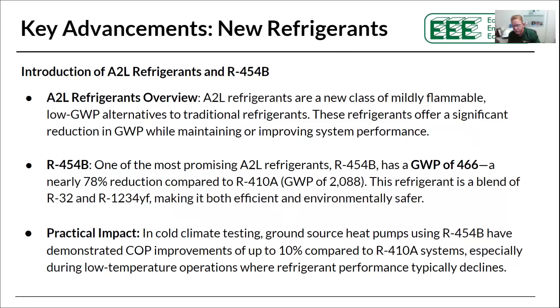The coolest thing about 454B is that in cold climate testing, it's having an impact on COP. As we see these new refrigerants come out, it's going to make an improvement to the performance of the equipment. Typically, over 410A, 454B adds about 10% to the COP. In the coming years, it'll be very interesting to see what refrigerants we use, but at this point, it looks like R32 and R454B are the refrigerants we're seeing coming out for ground source heat pumps and other systems as well.